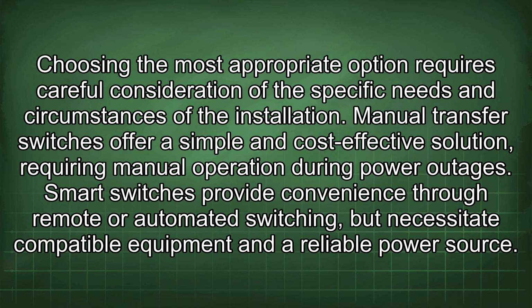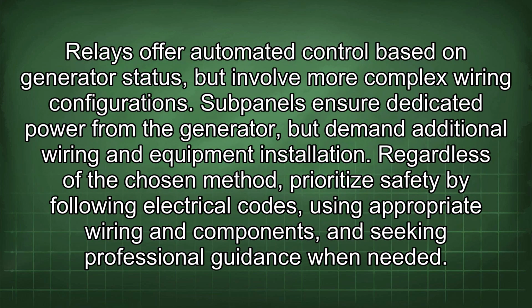Manual transfer switches offer a simple and cost-effective solution requiring manual operation during power outages. Smart switches provide convenience through remote or automated switching, but necessitate compatible equipment and a reliable power source. Relays offer automated control based on generator status, but involve more complex wiring configurations. Subpanels ensure dedicated power from the generator, but demand additional wiring and equipment installation.